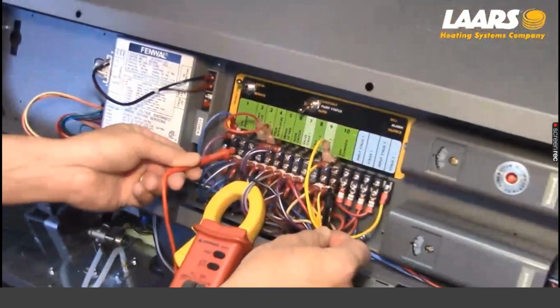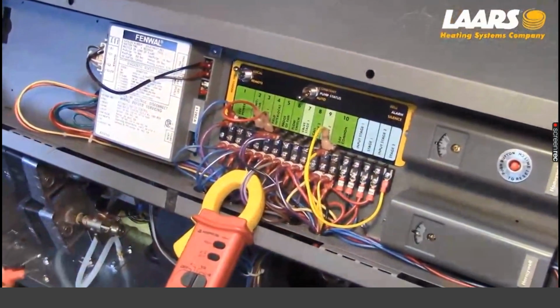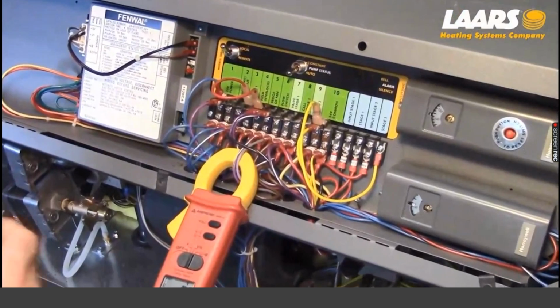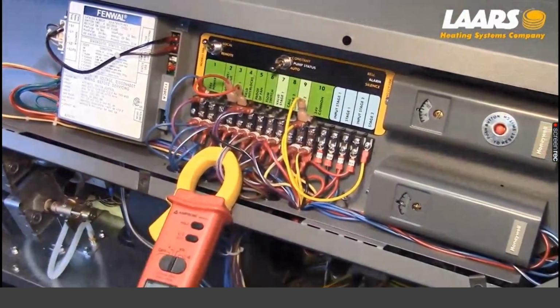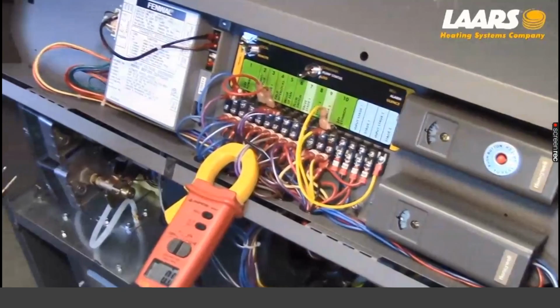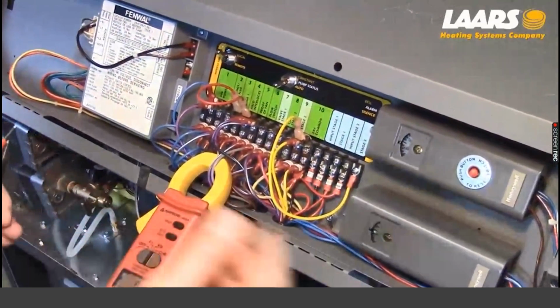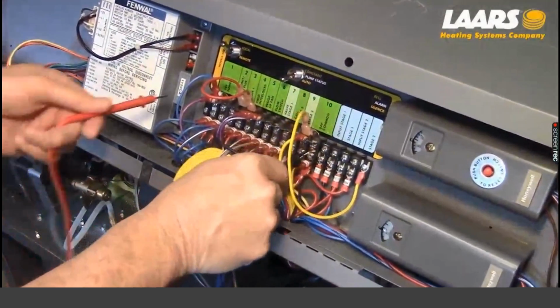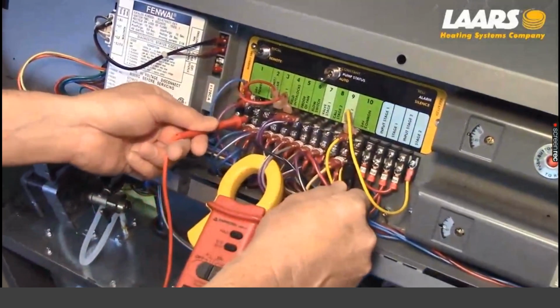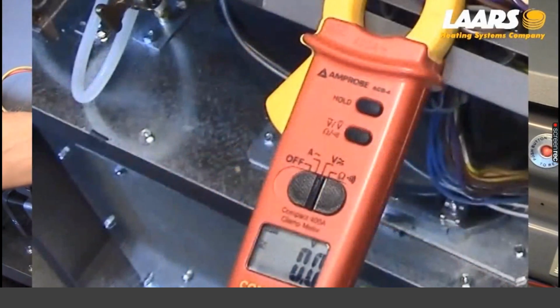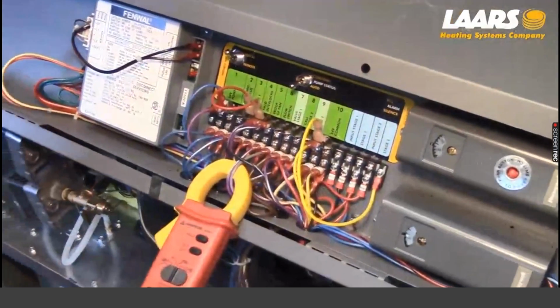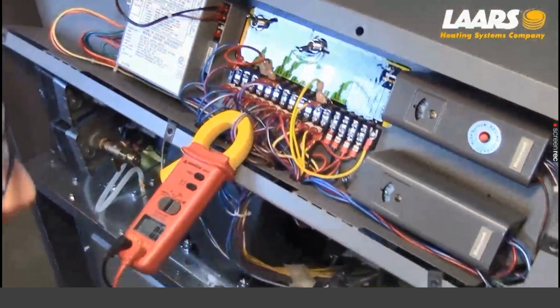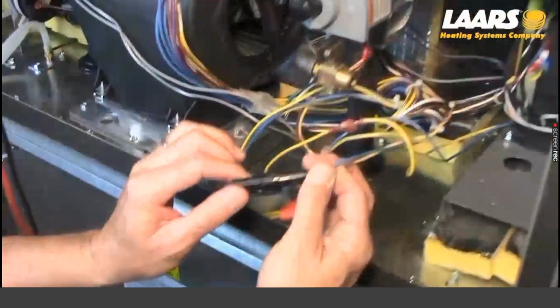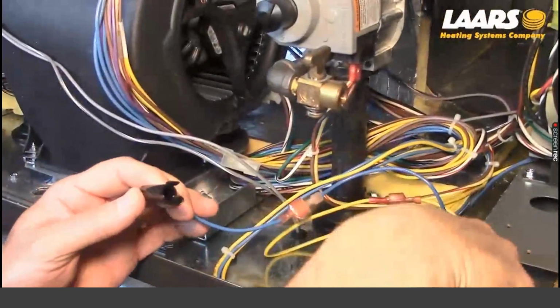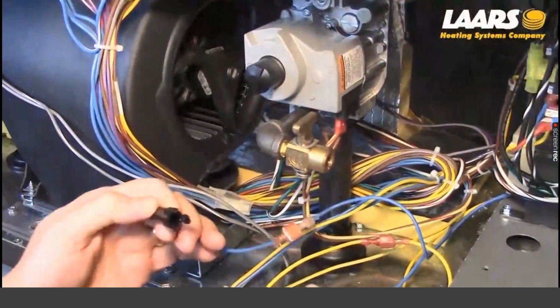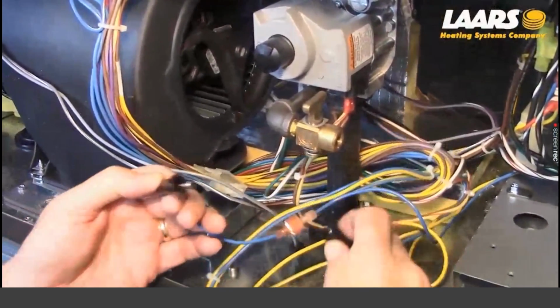Okay? So that's telling me that either I don't have line voltage or 120 volts coming in, or I have a blown fuse. So I'm going to double check my power, and in this case I do have power coming into the boiler, but as you can see, I do not have 24 volts between terminal 1 and terminal 10. So what's in line there is our transformer and a bus fuse holder. And for this example, I simply took the fuse out of the boiler, okay? So double check your fuse if that's the case.